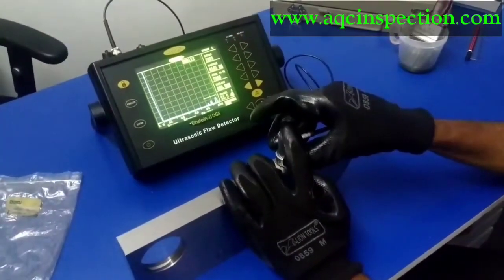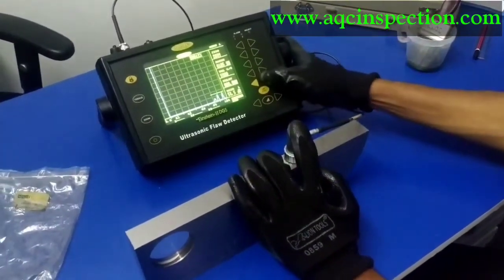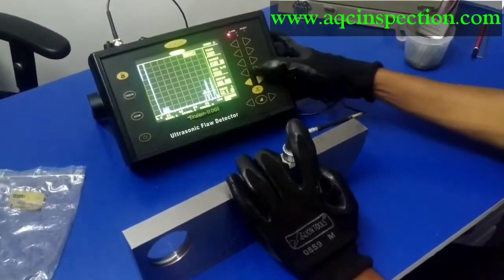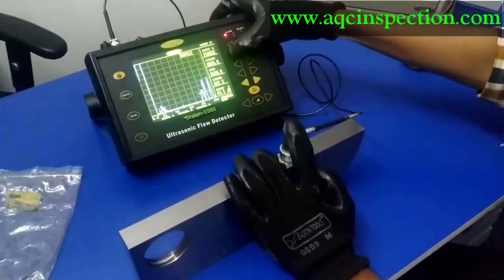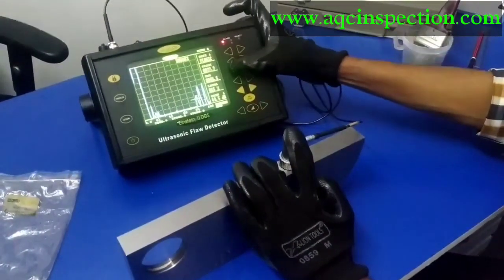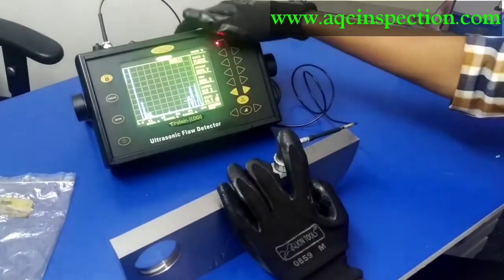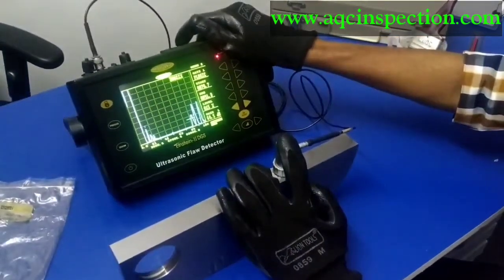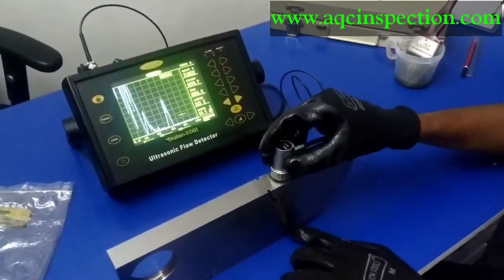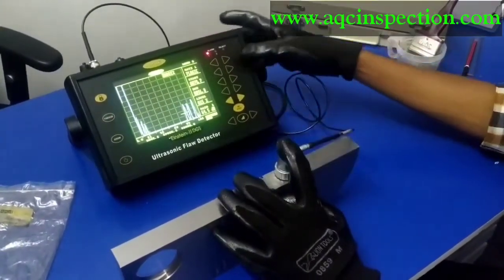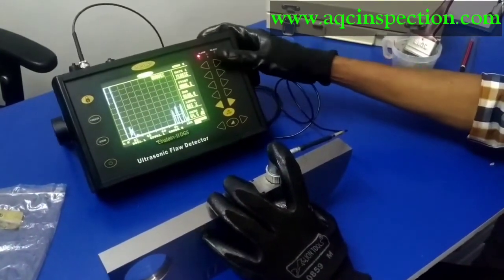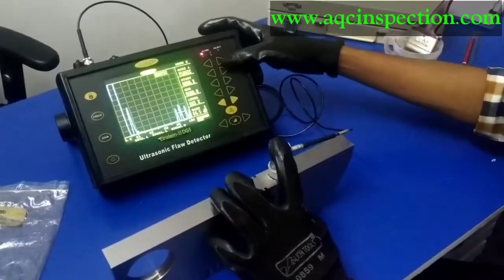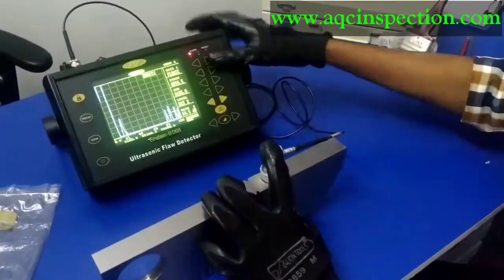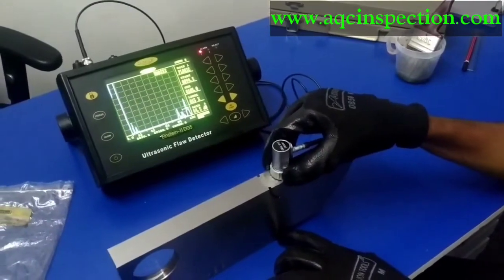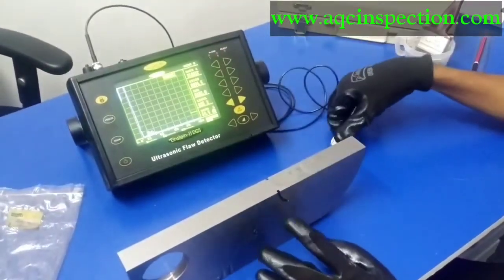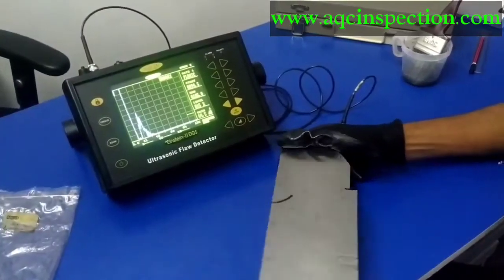As you can see, I'm getting 3 echoes on my CRT screen, so I'm going to increase my amplitude a little bit, and I'm going to adjust my gate. So the first echo I am receiving is 85.6, which is right, this one. This is the first echo, and the second one that I am getting is 91, which is this surface right here, and the last one is 100 mm, which is the back wall of this material. This is what we call the resolution check.